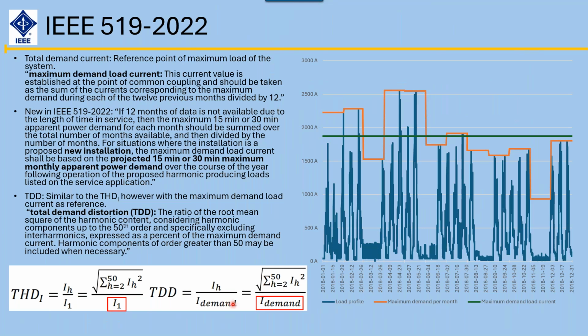The beauty is, since they've gone to the new standard, they're doing it over the demand. Now I'm looking at whatever the harmonics are over this number versus this number, and I get a real reading and a much more accurate representation. So a lot of times when customers tell me they've got a 40% THDI, I don't care, because I don't know what the full load fundamental current was. Okay. For greenfield projects, they've got provisions in the standard. If you don't have a year's worth of data, which most people don't, you can do it over whatever time period you have, or you can do a projection over 15 or 30 minutes. So that's what TDD is versus THDI. Very important concept.